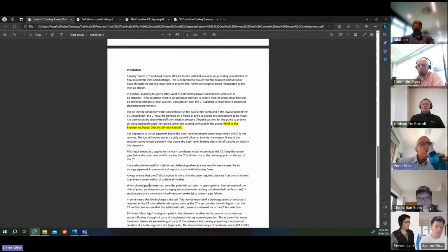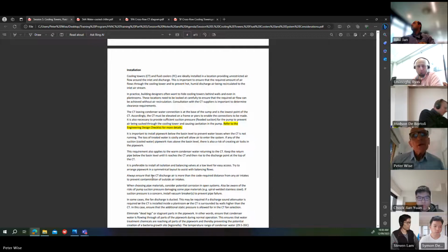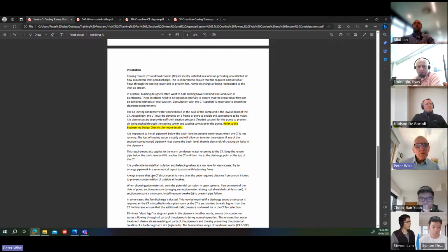Okay, and talk about installation. This is the design of the cooling tower. Well, there's a number of different options available, whether you're looking at cooling towers or fluid coolers or hybrid coolers. We need to make up our mind which type of system we want to use, depending on the rest of the system, whether we're using water-cooled chillers or whatever. And then we can give our requirements to the suppliers, so the likes of BAC, Evapco, and so on, and they will make some selections and give us some options. But we have to think about the installation requirements and talk to the suppliers about the installation requirements as well, because it's critical to get it right.